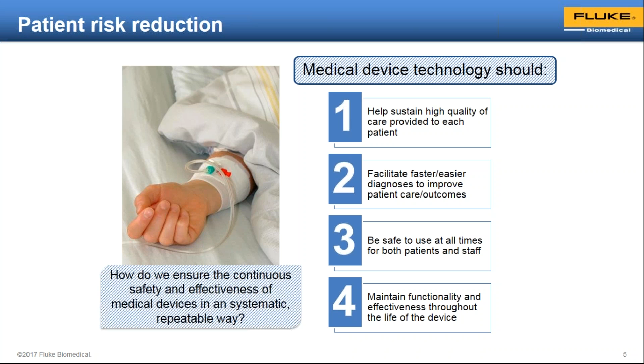Maintenance factors. So the manufacturer maintenance requirements are provided in the service manual of the medical device. And the recommendations are based on the device type, its design, and the components inside. And only the medical device designer and manufacturer really knows this best. And so we look to that work instruction, the service procedure, and preventive maintenance testing procedure from them, and that's found in the service manual.